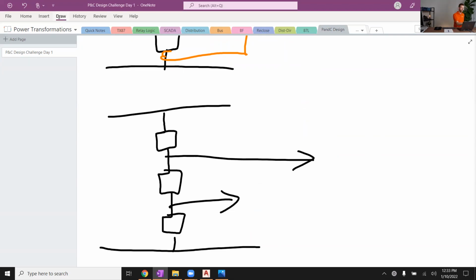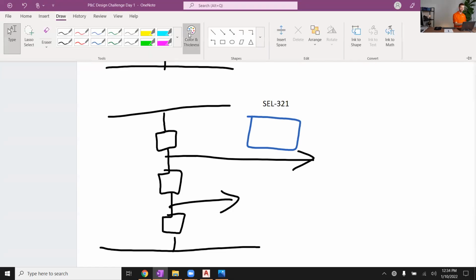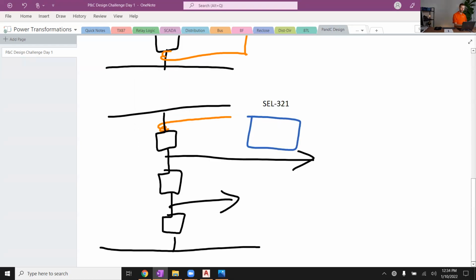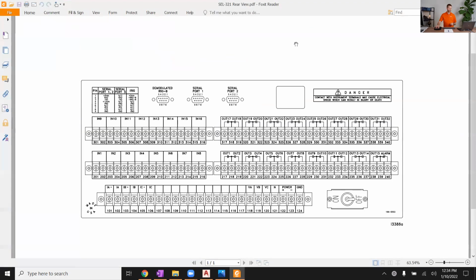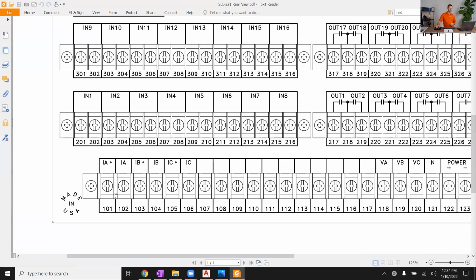And in the case of a line relay here, I'm going to just draw this relay this time. Let's actually say this is not a 421. I'm going to change it up on you. What if it's an older SEL 321? Well, we're still going to have 2 different sets of CTs coming here from line breaker 1 and line breaker 2. But if you've been around for a while and you understand some of these different legacy older era models, I'm going to pull up the back of a 321. I can find my diagram here, rear view. The back of a 321, I've only got 1 set of CTs that I can wire to. I don't have 2. So how am I going to handle that in a breaker and a half or a double bus, double breaker, or a ring bus application?